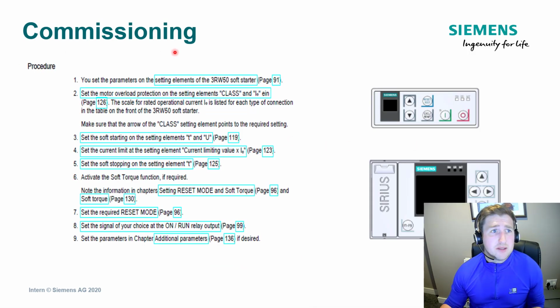In terms of commissioning the soft starter, it's highly recommended that you use an HMI screen. That's because the old way of identifying whether you have any issues during the commissioning process would be through LEDs on the front of the soft starter. They flash differently, the lights could be on permanently, they also indicate different colours, and those different combinations would indicate different faults. So it can be quite difficult and quite taxing of your time to look at the front of the unit to try and analyse what those faults are.